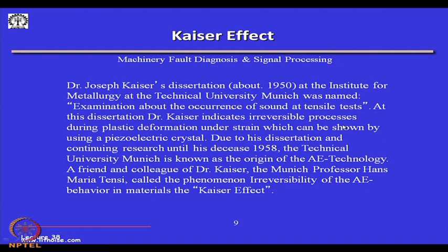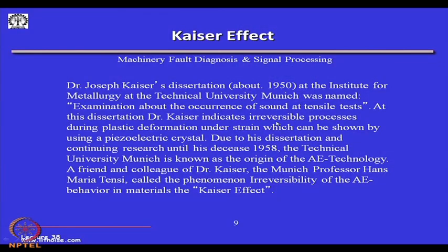There is another related effect in acoustic emission known as the Kaiser effect, named after Dr. Kaiser. It describes an irreversible phenomenon in the behavior of materials during plastic deformation in strain, which can be shown using a piezoelectric crystal. Because of the Kaiser effect, whenever the material is stressed beyond its earlier stress limit, only then will we have a meaningful acoustic emission signal coming out of the system.